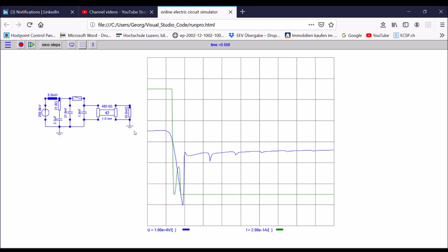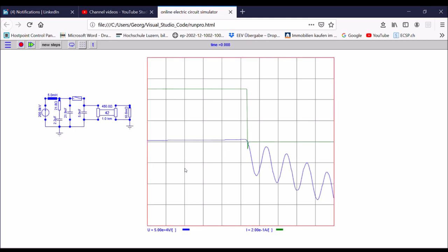This time it fails. You see that the post-arc current, which was a very small tweak before, has now grown up, so the heat produced by the arc is now so high that the arc reignites. So this is an unsuccessful current interruption for short line fault, and the model is the Cassie-Mayr equation, which is demonstrating how the thermal behavior of a breaker works. Again, to make the point clear, we have been looking just at the very initial phase of this TRV composed of two parts, the line side, which is this oscillation you see here, and the source side TRV, which would continue now to the peak of around 1.4 times the source voltage.